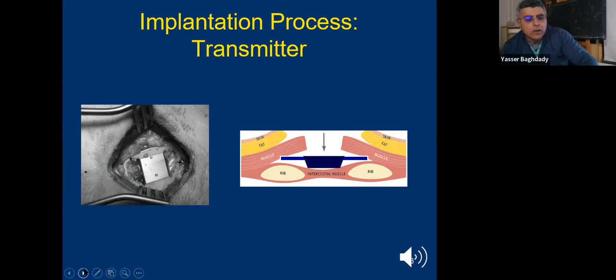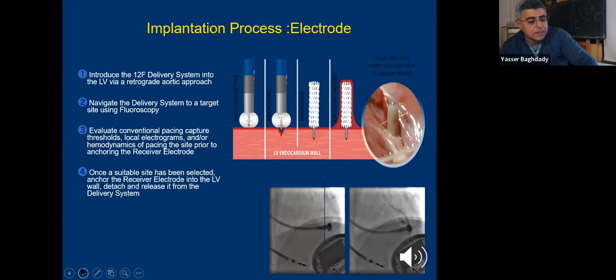The pellet, the electrode itself, is inserted through the sheath. We do look at it under fluoroscopy very carefully to make sure that we insert this tined needle, if you wish, that makes it anchored very securely to the LV endocardium. This is what it looks like in animal tests. And basically this will be a very, very stable electrode for pacing.